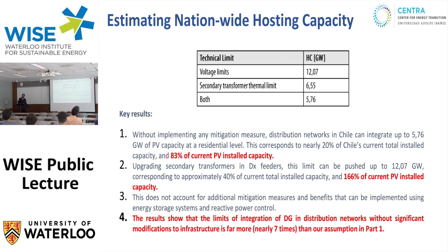Okay, but the secondary transformer—those are the ones you see on the street, right? It's not in the substation, it's downstream of the substation. So my perception, though we didn't run the study again, is that that's not what's going to limit DG penetration. You just change the transformer—it's not going to add significant extra cost, right? So I think this limit is not hard to overcome, and rather cheap.